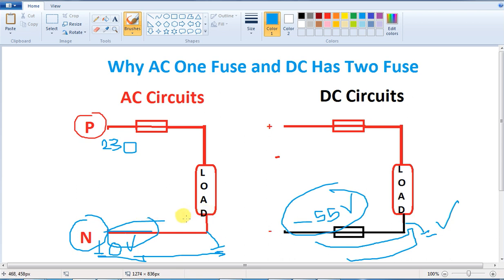If you look at the AC case, we don't need a neutral side fuse. In the final analysis, neutral is zero potential. But negative in DC has potential. So if there's a fault in the neutral, there's no risk. But on the negative side in DC, we need protection. That's why DC has two fuses and AC has one fuse.